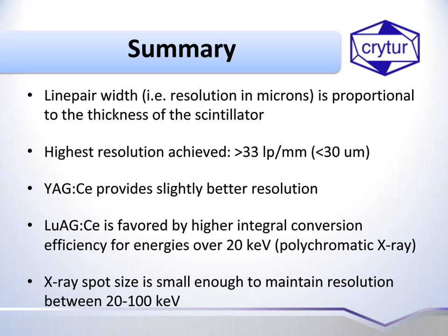What are typical thicknesses of the high-resolution scintillators? It's a tricky question. We can start from 5 microns of thickness for YAG and LuAG to, say, 100 microns for imaging, or millimeters, but it has an effect on the resolution. For the greatest resolution, you need as thin a scintillator as you can, so 5 microns would be the best.